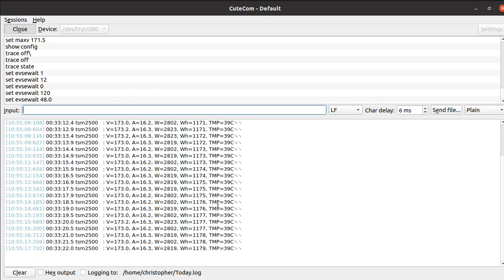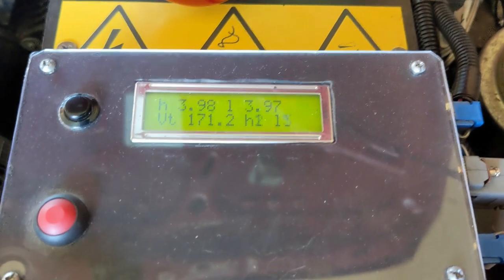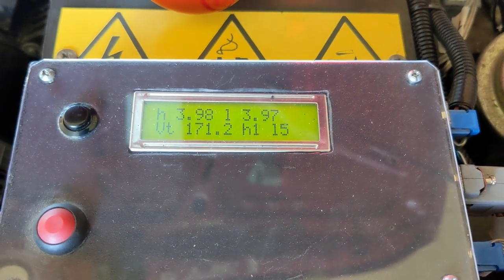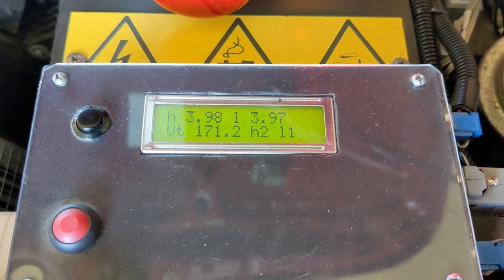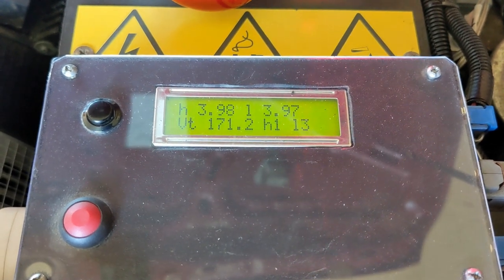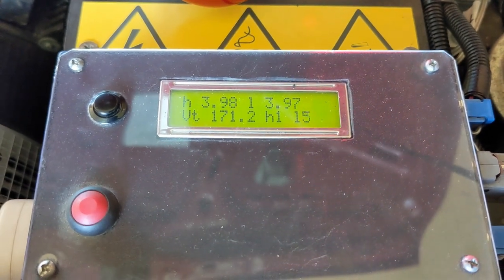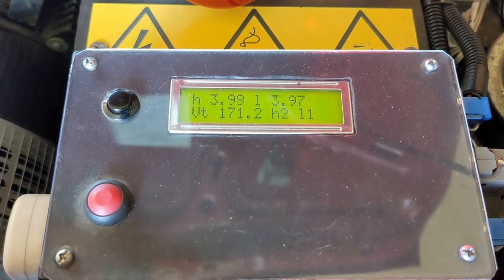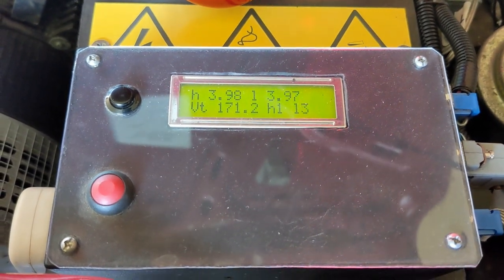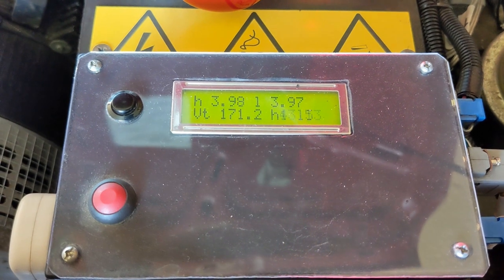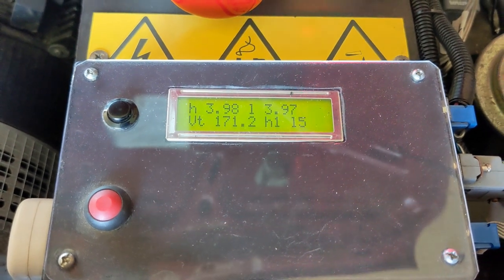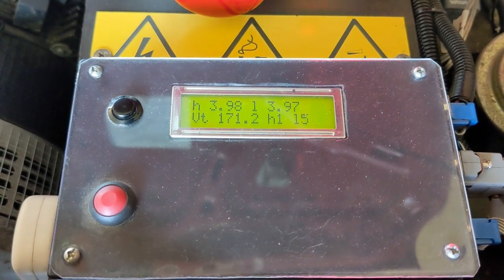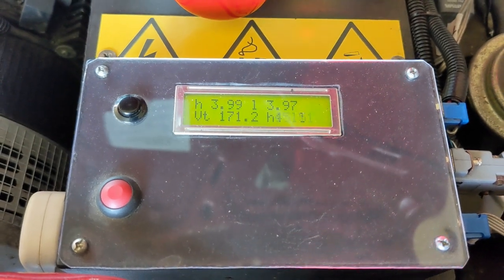Let's go check what the BMS says now, because these used to be quite different. So 173.0 on the charger, and there's 171.2 on the BMS. So yes, they're still quite different. You'd expect it to be a bit different under charge, there's 15 amps being drawn at the moment, so it should be higher while charging, and you'd expect that to settle down a bit when the current draw starts to go down, but we'll see how we go.